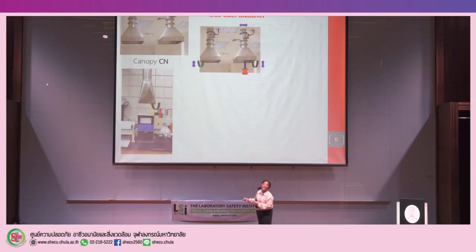This is the burning part where you generate the vapor, the petrol vapor. But if the canopy is here, it's not going to go anywhere. It has to be right above it and as close as possible, because heavy metal vapor is very heavy. So if it's like this, it's not going to work at all.